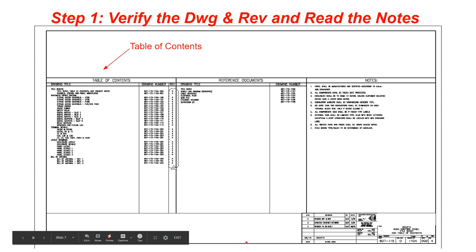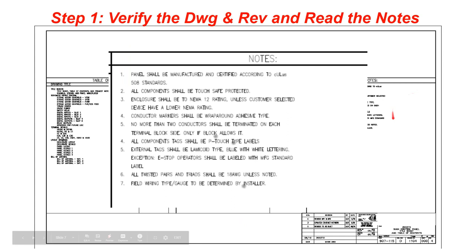From there you'll see the table of contents, which tells you what you're looking for and where it is in the drawing set. The notes section is something you really want to pay attention to — it's basically the ingredients of what we're using to make the drawing set. In this case it's following UL 508, and it gives you information on conductors, the enclosure, NEMA ratings, etc.